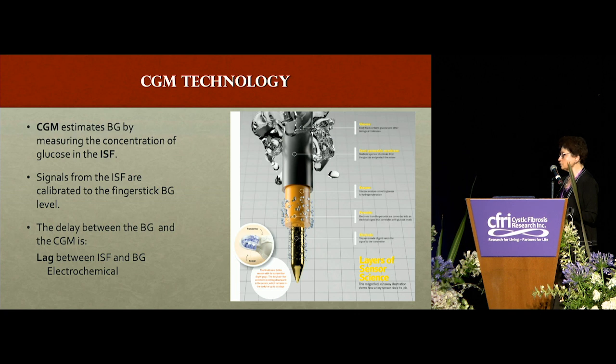The sensor is protected with a membrane, allowing only glucose molecules to get to the next layer, which is the enzyme. This enzyme has the ability to oxidize the glucose, producing electrons that are detected by this little electrode. If you can barely see the tiny sensor, this is a very magnified cross-section of it. Technology is amazing.